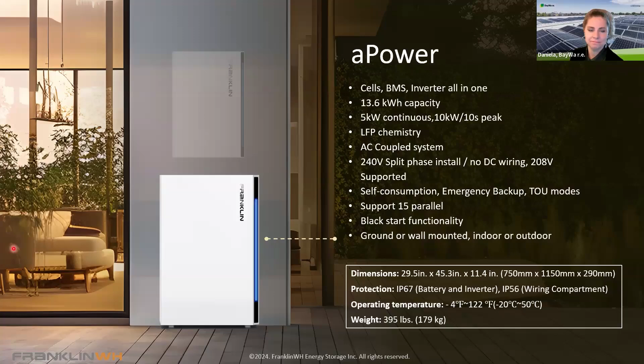This slide demonstrates the question earlier about stackability. As you stack the batteries, the capacity increases: 13.6 times 2, times 3, up to 204. Same thing with inverter output: we start at 5, and as you stack them, at 8 batteries we max out at 38.4, which is 160 amps. So our controls set the limit at 160 amps. The same applies for surge protection for starting appliances; it just doubles for each one, capping out at that same level of 160 amps times 2.